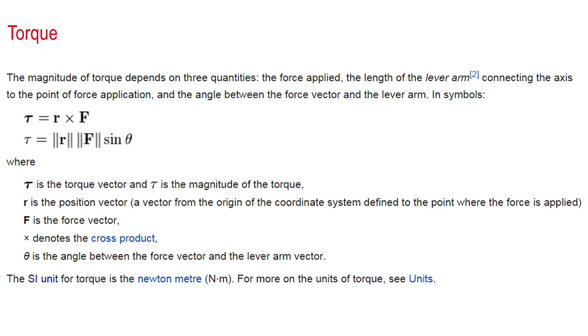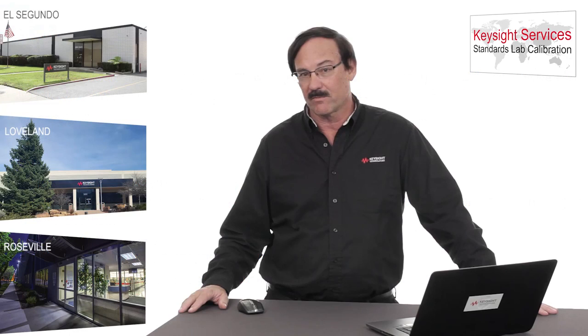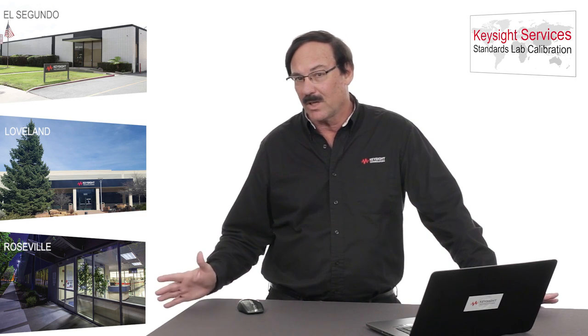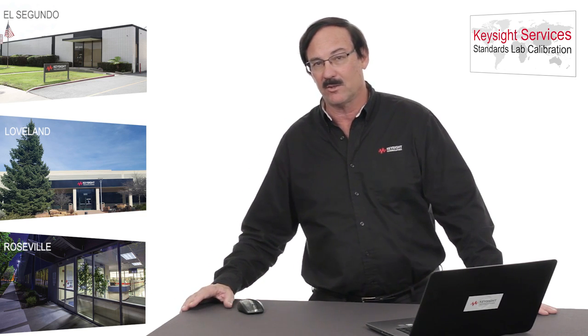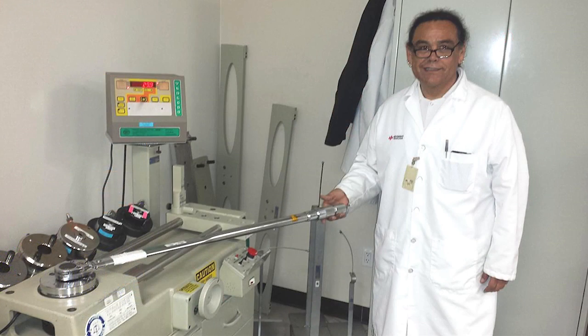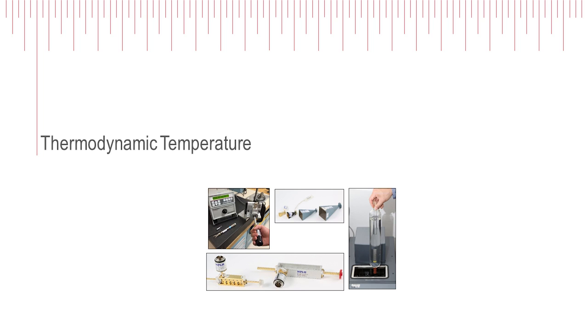Torque is the cross product of the length times the force. And it's expressed in Newton meters in SI units, but in the English system it can also be pound inches or pound feet. Once you can accurately measure mass and therefore force, and you measure length, you're in a position to calibrate devices which can measure torque. So let's take a look at how they make temperature measurements at our El Segundo Center of Excellence.